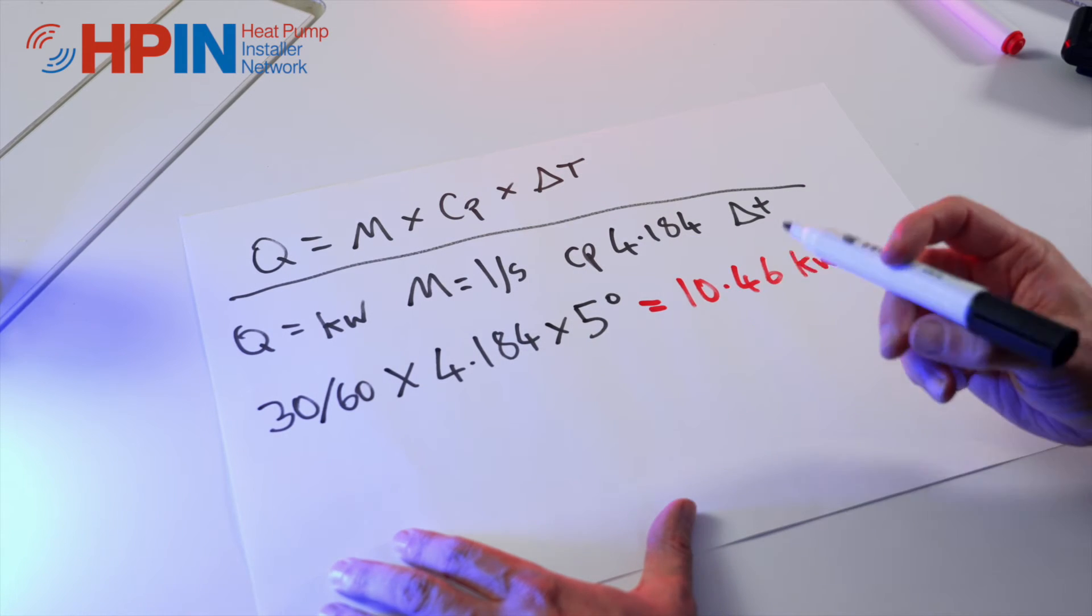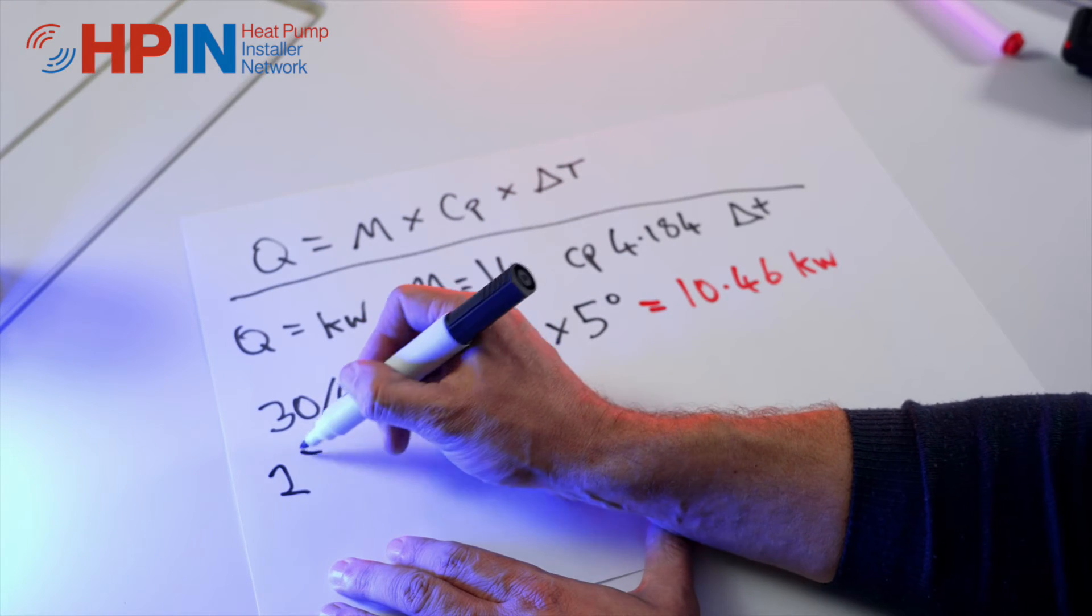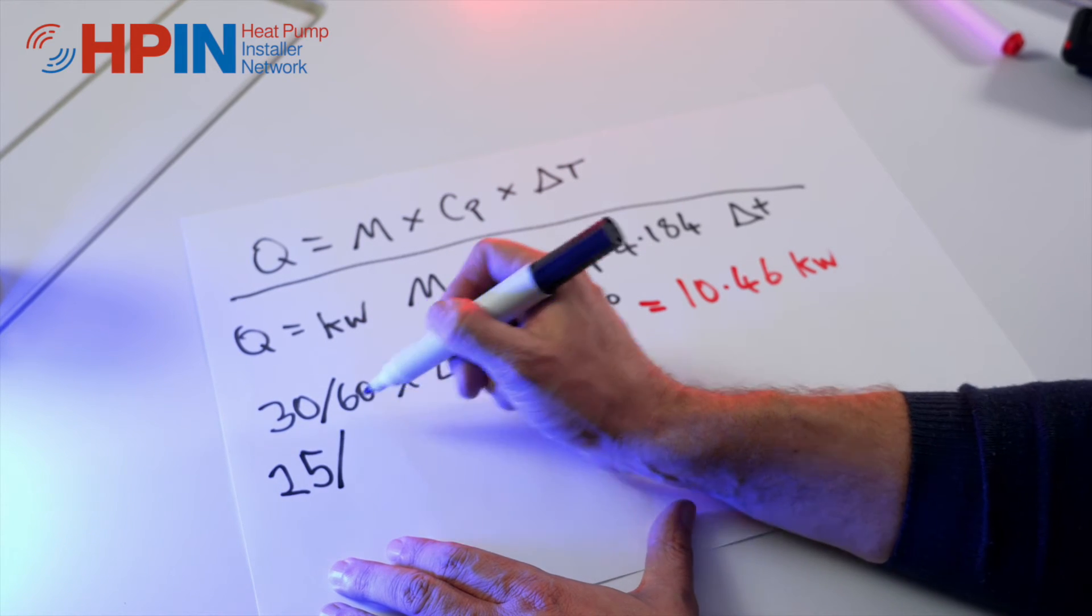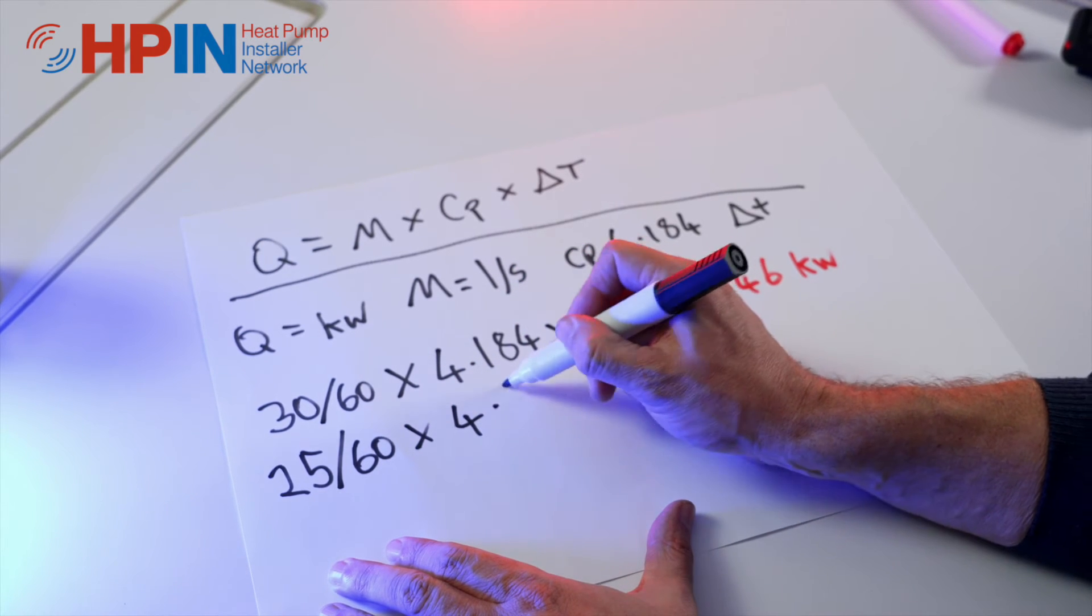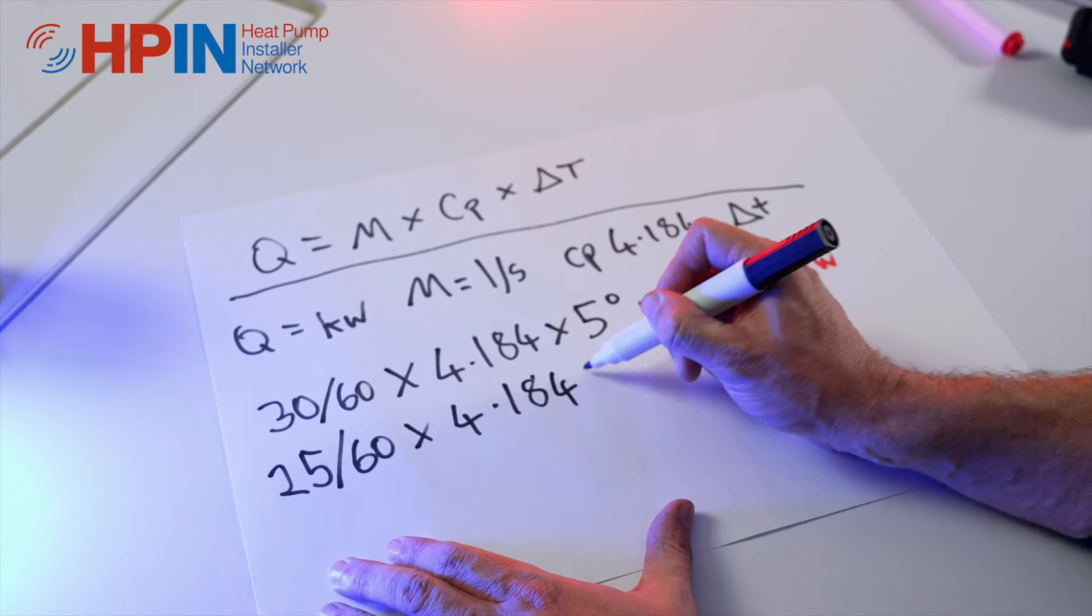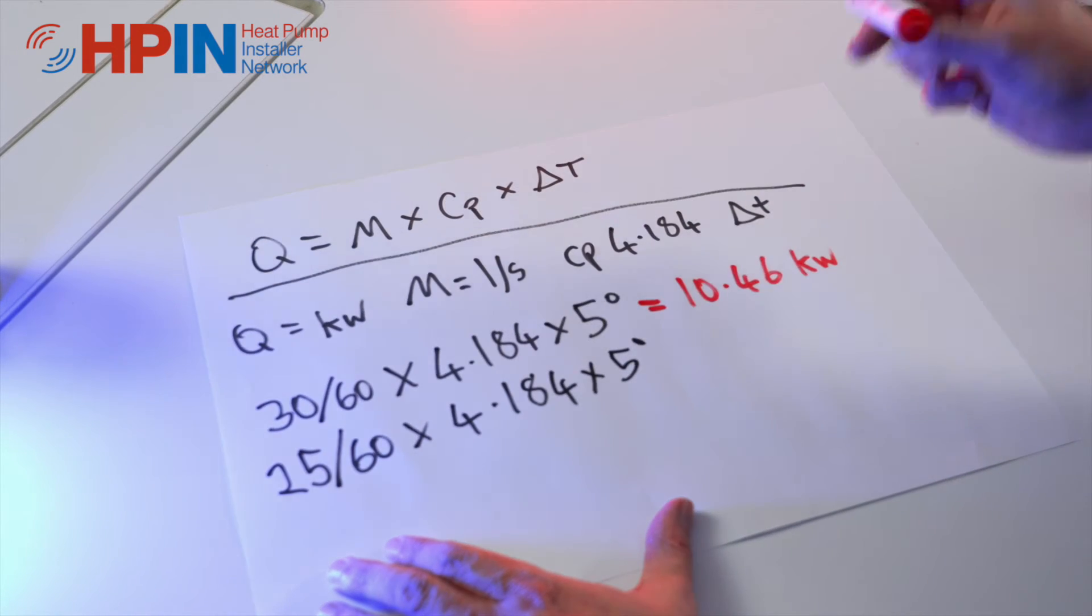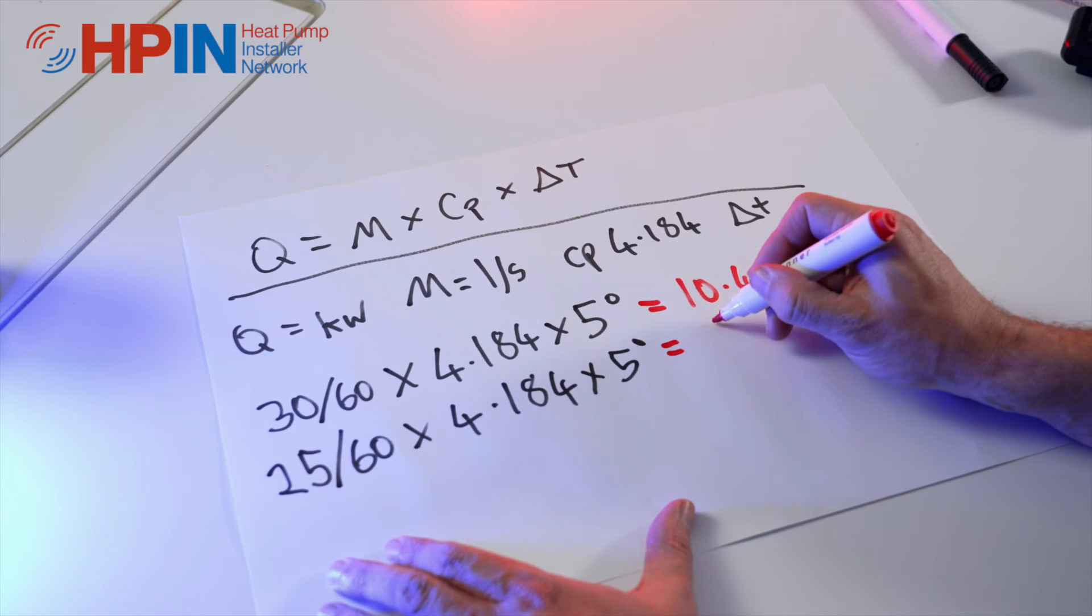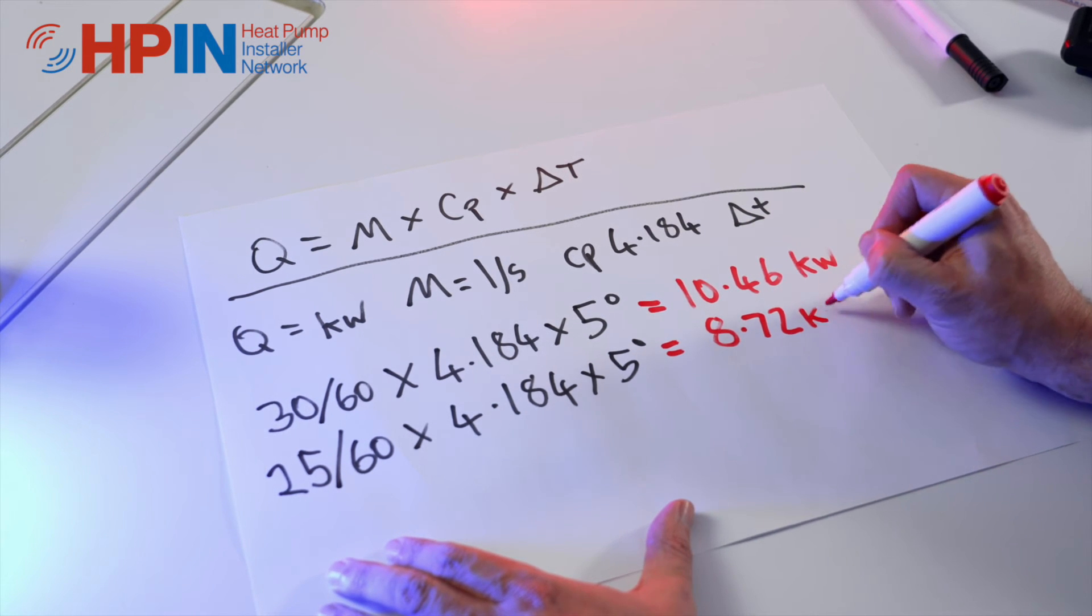So now I'm going to change the flow rate. Let's just drop it by say 5, so we've got 25. We're going to divide that by 60, times it by 4.184 times that by 5 for our delta T. And that is going to give us 8.72 kilowatts.